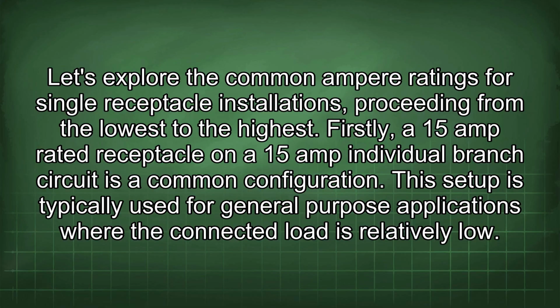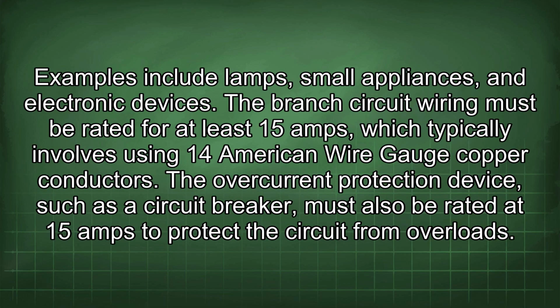This setup is typically used for general purpose applications where the connected load is relatively low. Examples include lamps, small appliances, and electronic devices. The branch circuit wiring must be rated for at least 15 amps, which typically involves using 14 American wire gauge copper conductors.